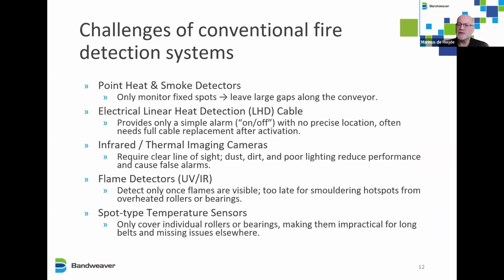So, what are the challenges of conventional fire detection systems? Because there are various types of fire detection. It's not just fiber optic linear heat detection, of course. So first of all, you've got your typical point heat and point smoke detectors. They will only monitor an area at a fixed spot, and if you have very long conveyor belts, unless you install a hell of a lot of point detectors, you will leave some gaps along this conveyor. So for longer conveyor belts, point heat and smoke detectors are just not very practical.